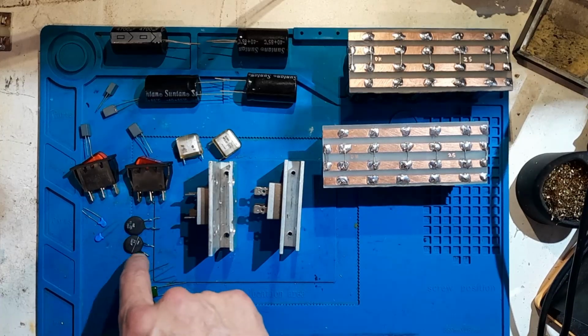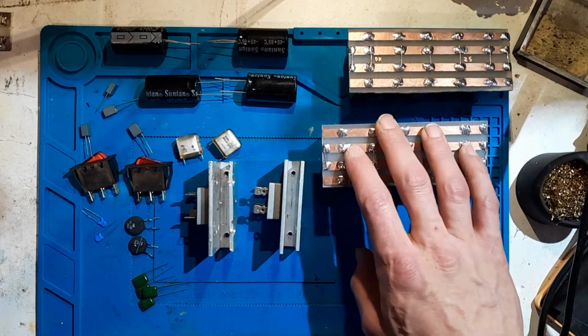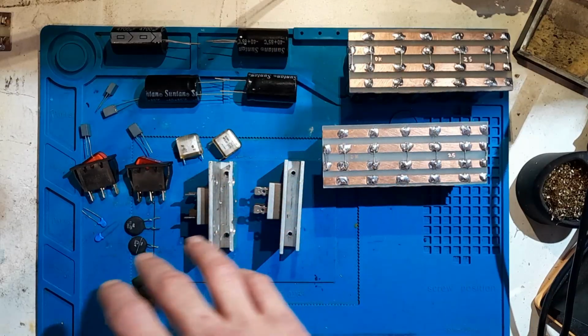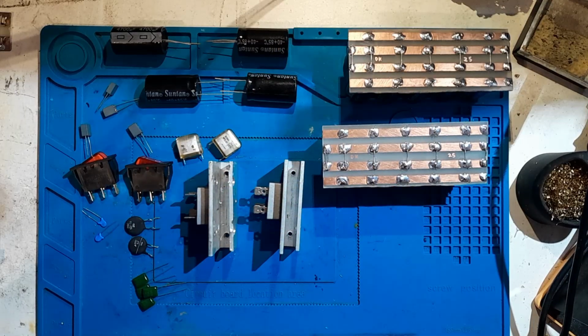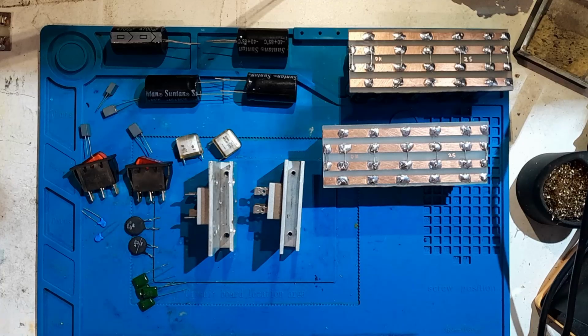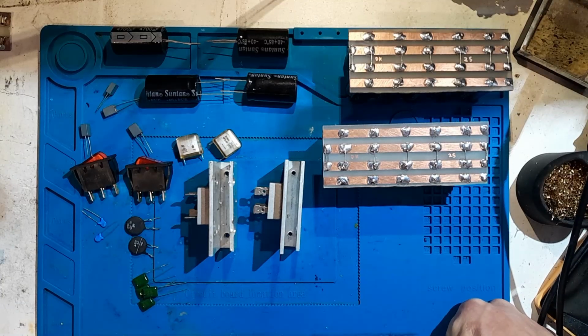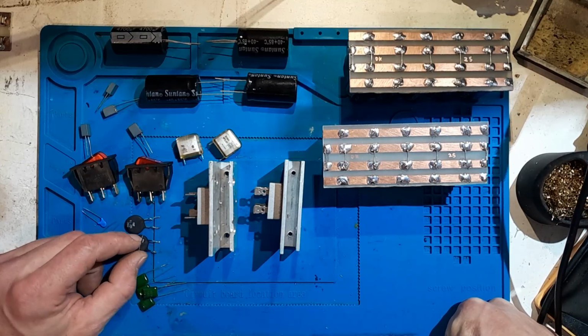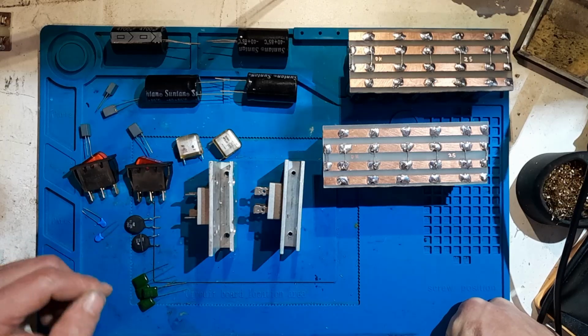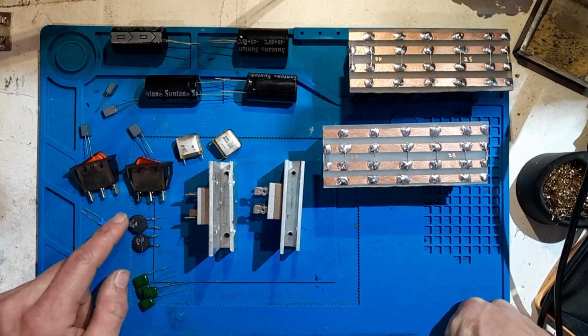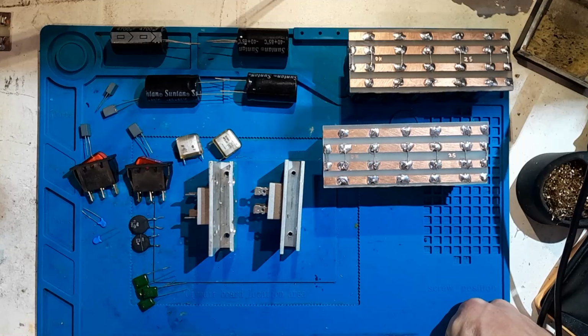That's for my inrush current protection, because I've got such a massive cap bank and a huge transformer, I'm expecting a pretty big inrush current. I don't want to have to oversize the main fuse to a point where it's not really a fuse anymore, so I want inrush current limiting. I'll be doing tests on this under load, looking at the volt drop on them and how warm they get, that sort of stuff. If it's not going to work, I'm not going to do it.